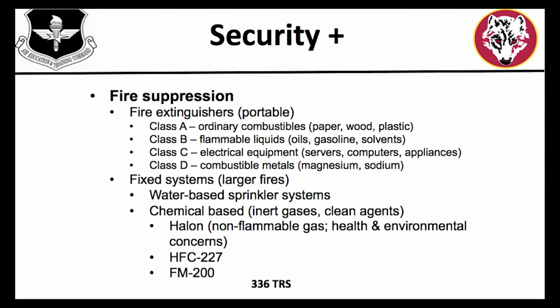Now, they too are going to be within a fixed system, but instead of releasing water, they're going to be using chemicals. Some common ones we see here, they're going to fall into this whole inert gas area: halon, HFC 227, and then FM 200. These are all considered clean agents. Now, I say clean agents. Halon's been around for ages. They've usually started going around as a replacement for those.